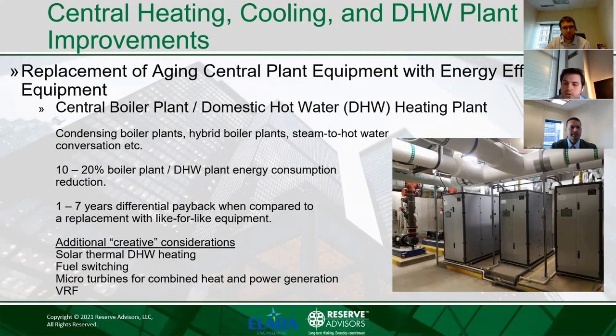It is also important to note that there are additional creative options that can be investigated at this phase. These can include fuel switching if there is conventional electric heating equipment. For instance, this would include switching from electric heating to natural gas heating. Just an example, in order to produce the same amount of energy to provide heating or cooling, using electricity is almost 3 times more expensive than natural gas if a conventional electric heating equipment is being used. That doesn't mean all electric equipment is costly. There are energy efficient systems such as VRF systems, which I'll mention.